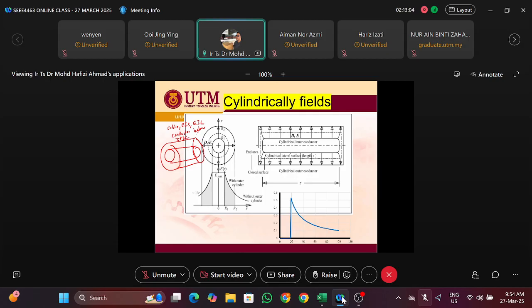If you visit a power plant, you might see that they are using the IPB in order to connect between the generator and step-up transformer. So in between, to connect the generator and step-up transformer, they are using the IPB. It's just like this cylinder, with a bus bar conductor inside, and it's actually insulated by a porcelain insulator.